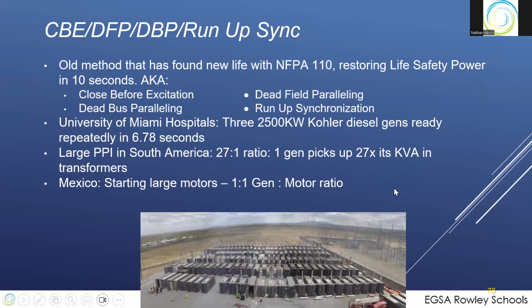In Mexico, starting large motors, you got a 1-to-1 ratio. They're actually able to start a 100 kW motor on a 100 kW generator, at the end of a long, soft line where they couldn't get there otherwise, and it worked.